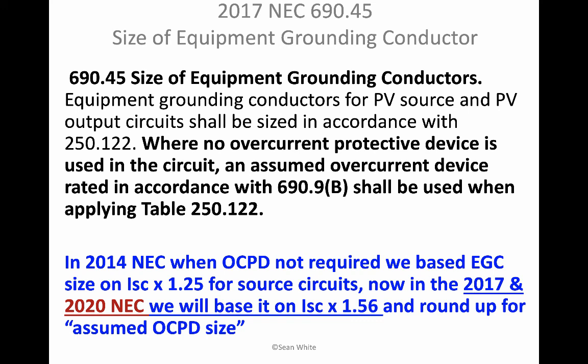The only time that you do 1.56 is for source circuits and output circuits. That's things connected directly to wild PV. Wild PV is PV that gets more current as it gets brighter, and if you shined a bunch of mirrors on something, it would get more current. But if you shined a bunch of mirrors on a PV module connected to a DC to DC converter, that DC to DC converter will electronically limit the current. So therefore, you don't have a short circuit current and a 1.56 with a DC to DC converter.